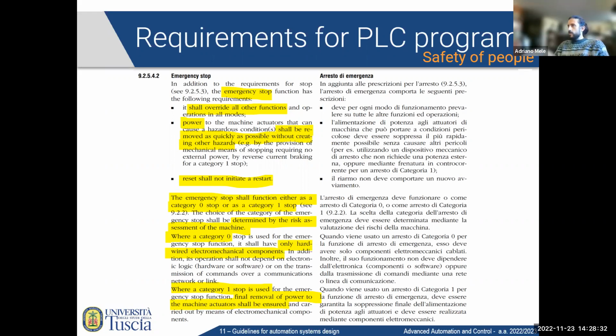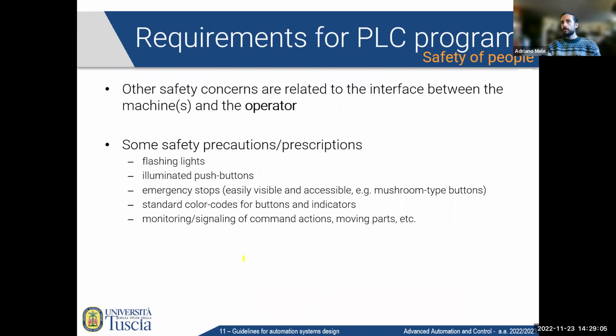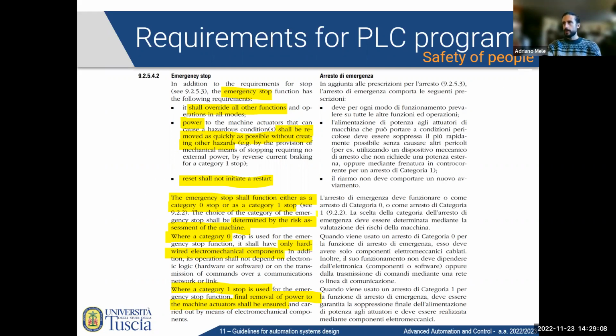And that's, of course, just common sense. Imagine someone gets stuck in some machine, you press the emergency stop, then someone else comes along and maybe presses it again because they think it still needs to be pressed, and it unlocks, and maybe the machine starts again and causes some damage. That's not how you expect it to operate. If you want to start it again after an emergency stop, you want to do it explicitly, on purpose. And an emergency stop can only be a category 0 or category 1 stop, where the choice is determined by the risk assessment of the machine, of course.